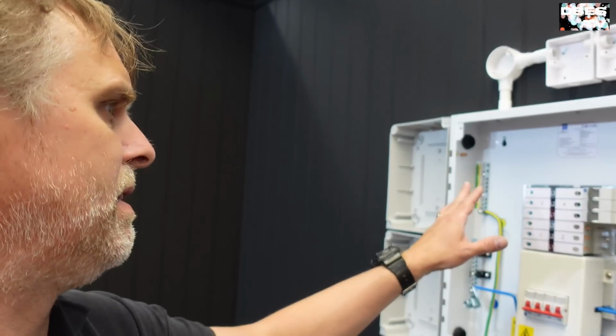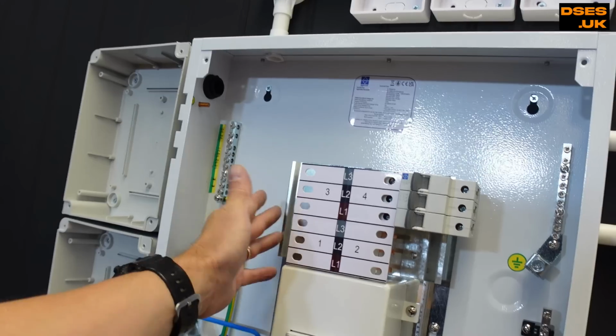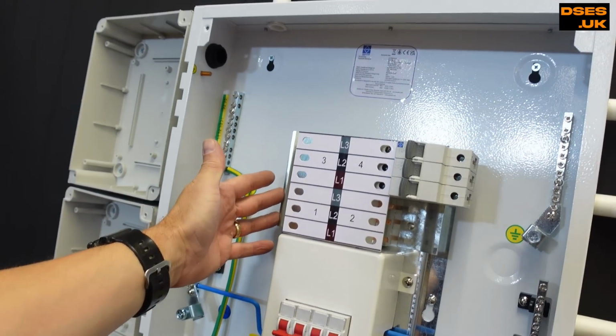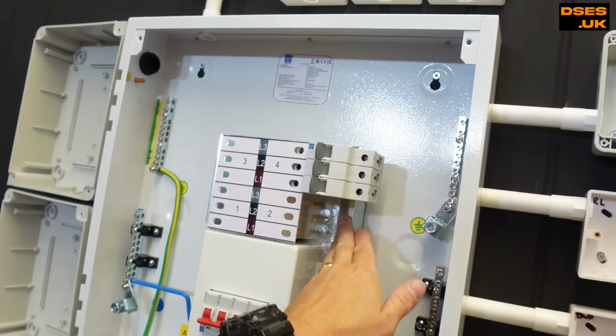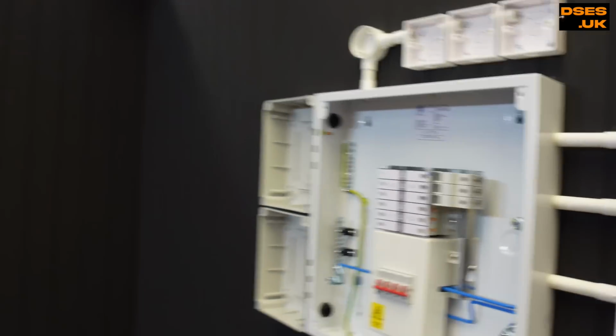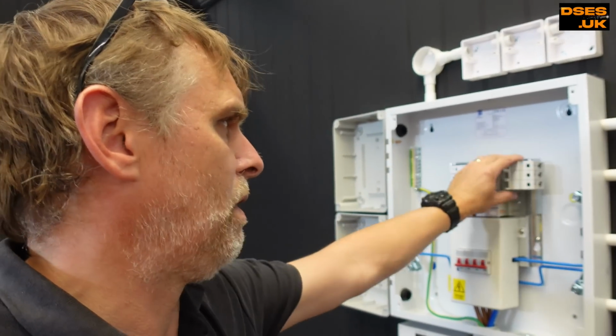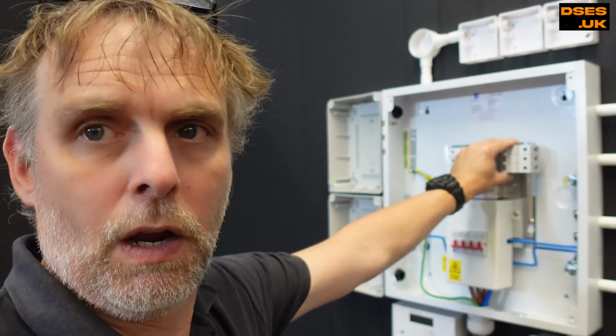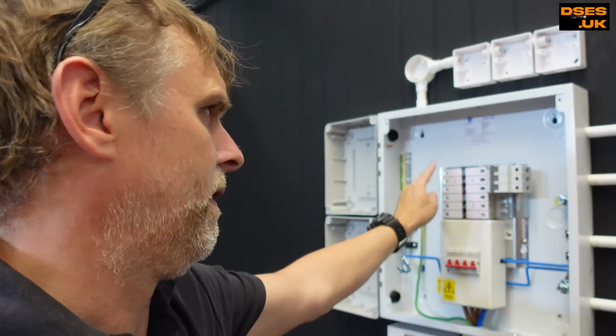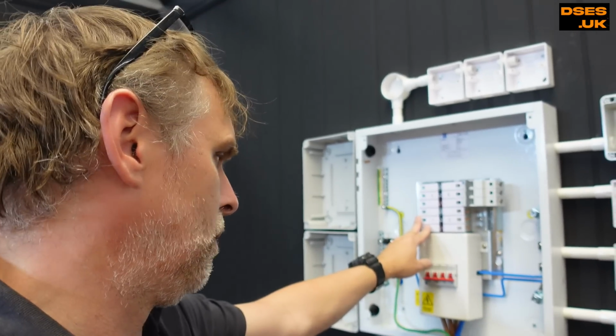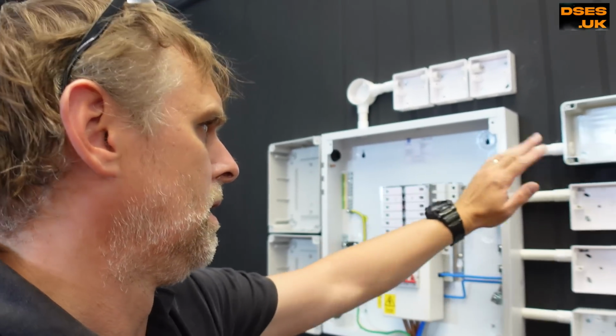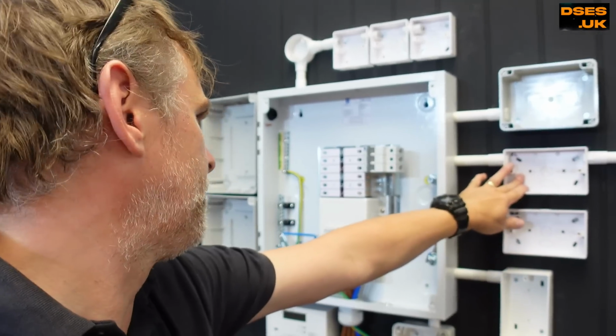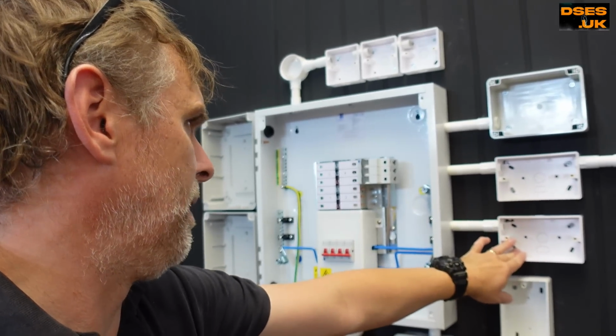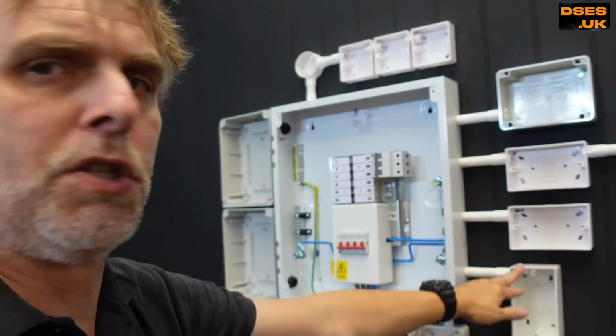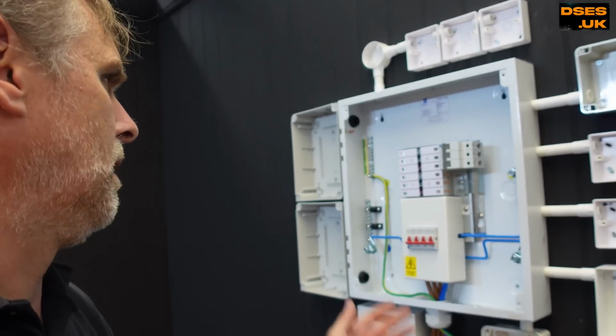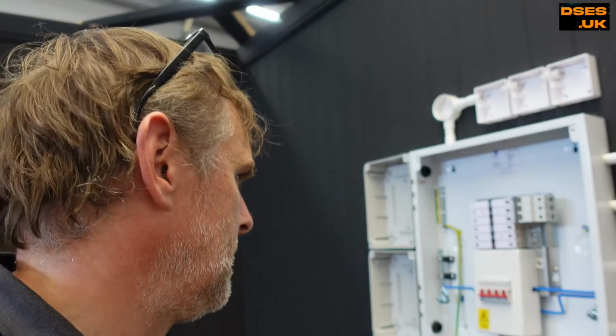So what I've done here is the conversion kit, which is just the DIN rail bracket. I've put a 6 kiloamp one on the left and left the original 10 kiloamp one on the right, which means my 2 three-phase circuits are going to go on the right side of the board, and the left side is going to feed a bunch of single-phase circuits. That'll feed the sockets via an AFDD, the radial socket via an RCBO, the lights via an RCBO, the shaver socket via an MCB, and we'll have a couple of spares.